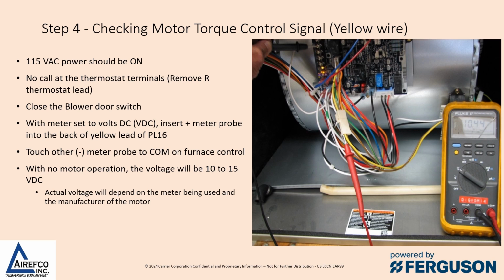Next, we're going to check the motor torque control signal on the yellow wire. Our power should be on. There should be no call at the thermostat terminals. Close the blower door switch. With the meter set to volts DC, insert the plus meter probe into the back of the yellow lead of PL16. Touch the other negative meter probe to common on the furnace control board. With no motor operation, the voltage will be 10 to 15 volts DC. Actual voltage will depend on the meter being used and the manufacturer of the motor.